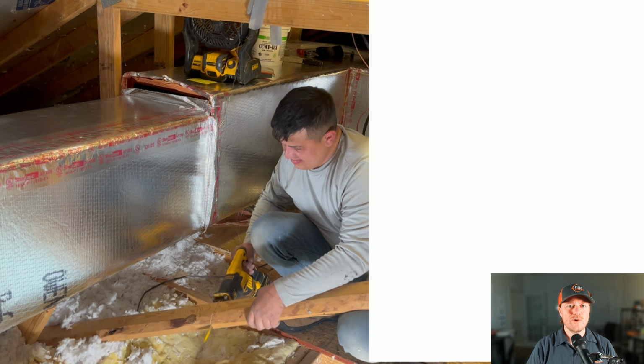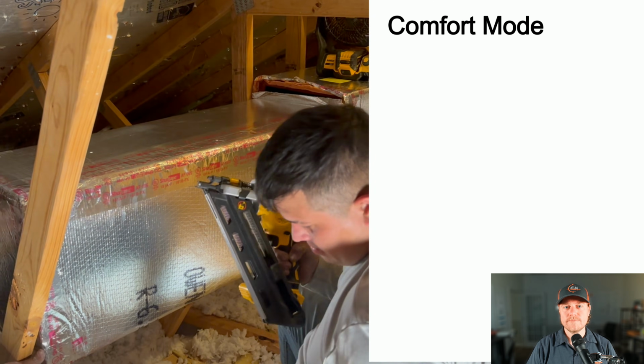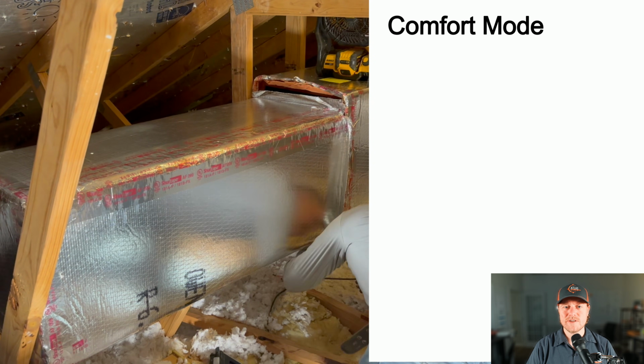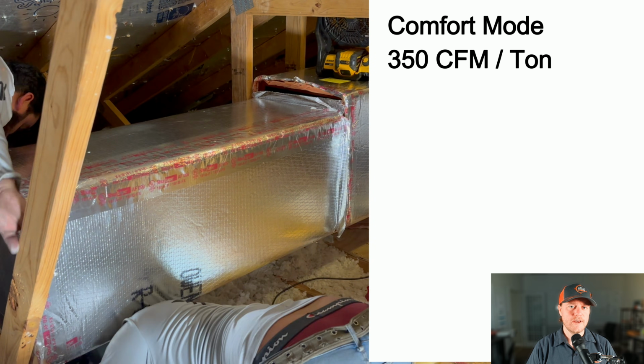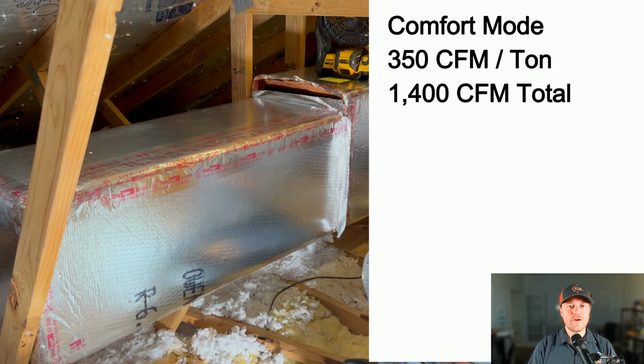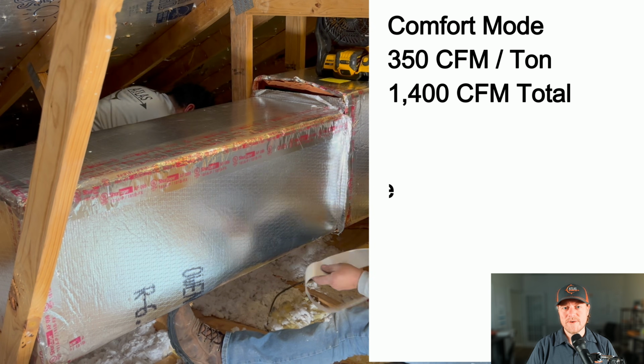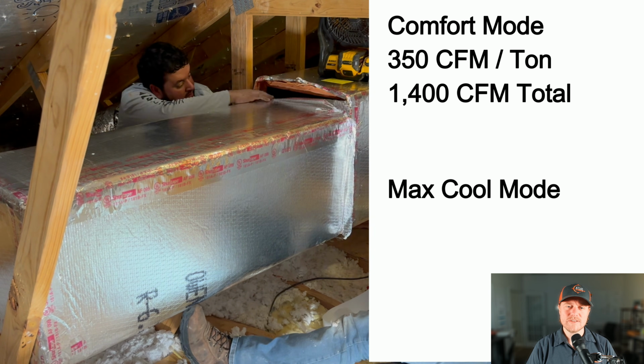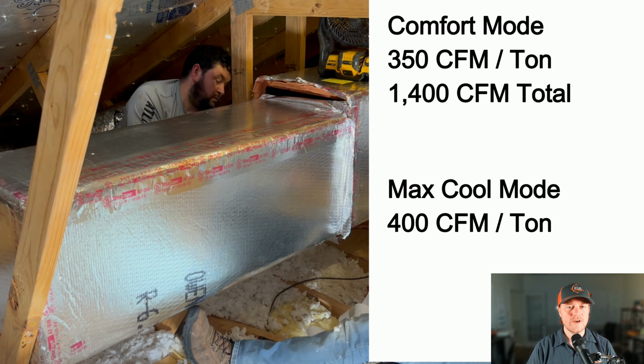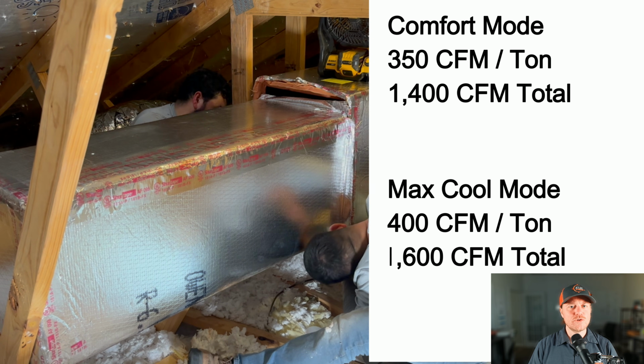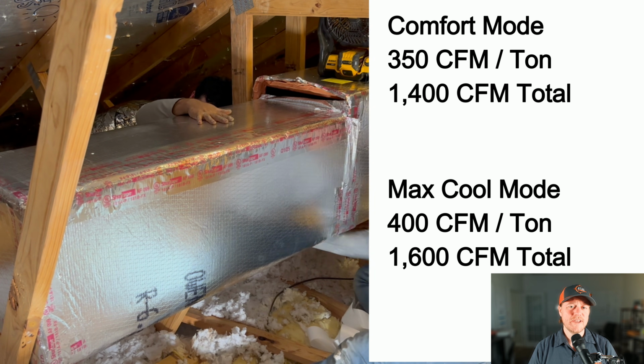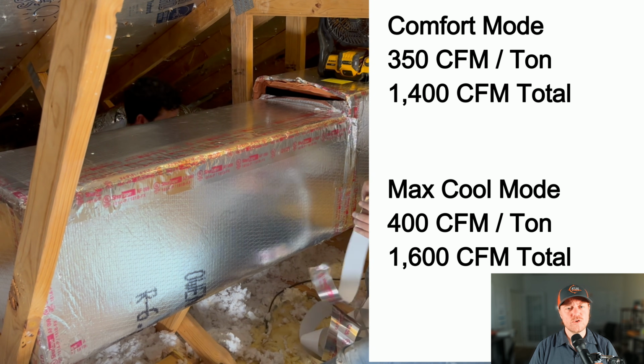The first test I'm going to have the system set in comfort mode. Comfort mode maxes out the system at 350 CFM per ton, or 1400 CFM of airflow. Then I'm going to do it again set to max cool, which is going to allow the system to push 400 CFM per ton, or in my case, 1600 CFM, which is going to give us a more apples to apples before and after comparison.